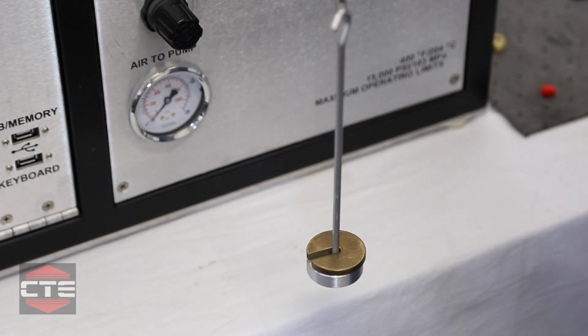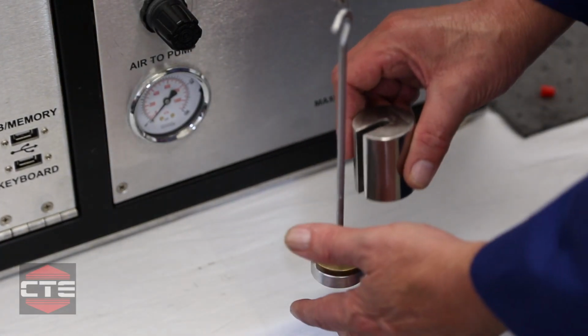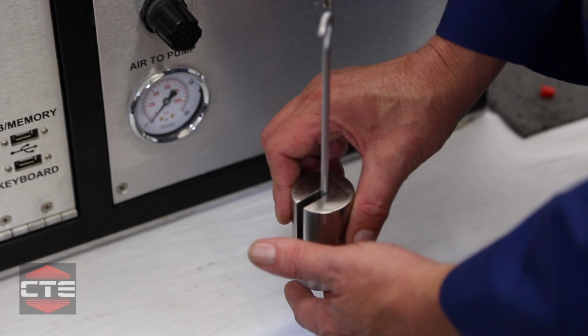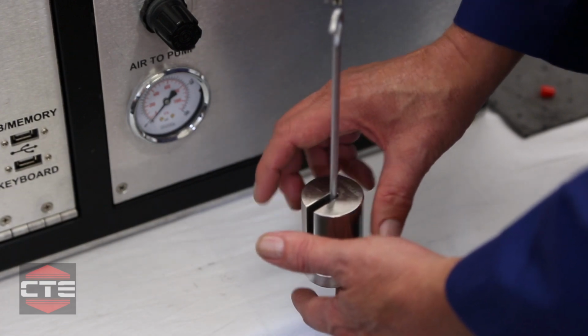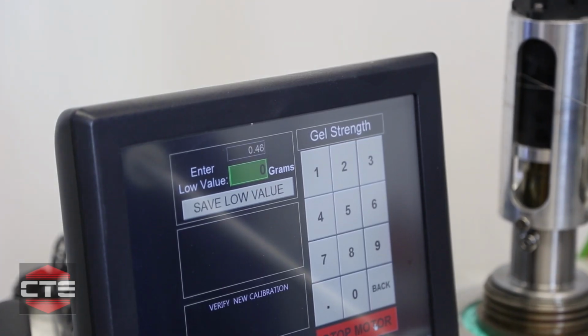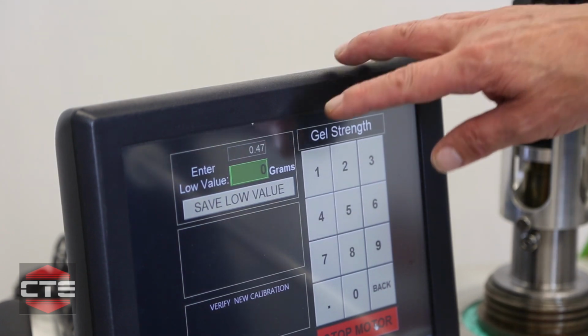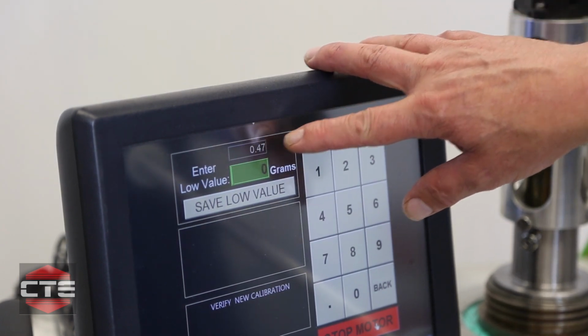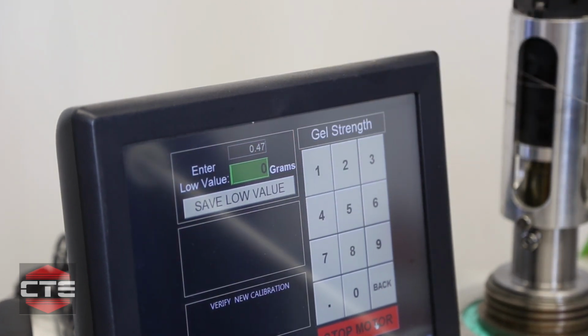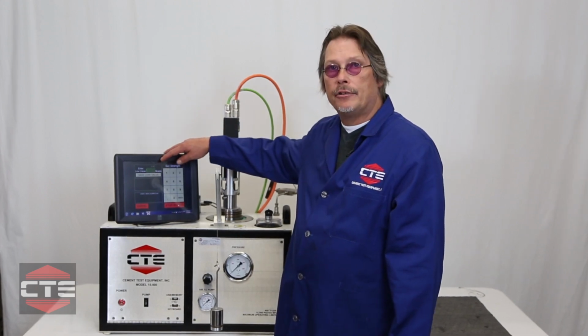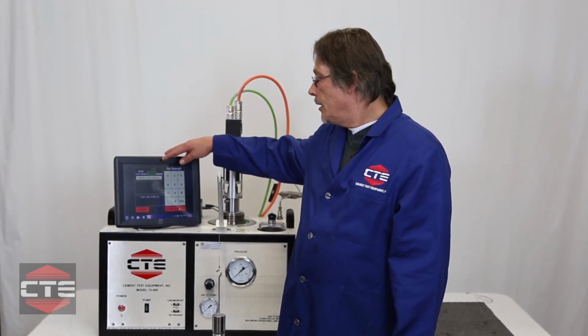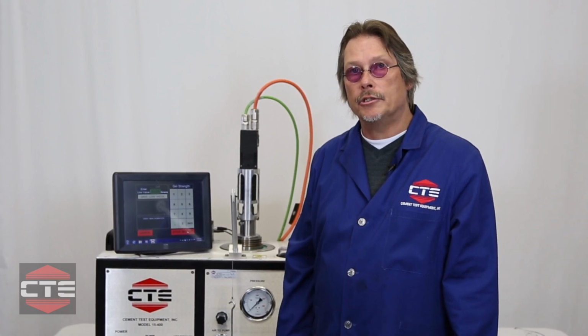Okay, now that my raw value has stabilized, I'm going to add 500 grams to the weight holder, and then again you can watch your raw value increase with the additional weight, and again we're going to wait until this value stabilizes. My raw value has stabilized to 0.47. If you personally are having problems getting your raw value to stabilize to one value, the last section of this video will cover reinstalling your MIT system files, which should be the solution for that problem.